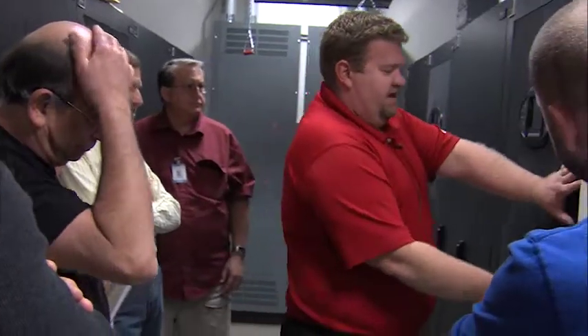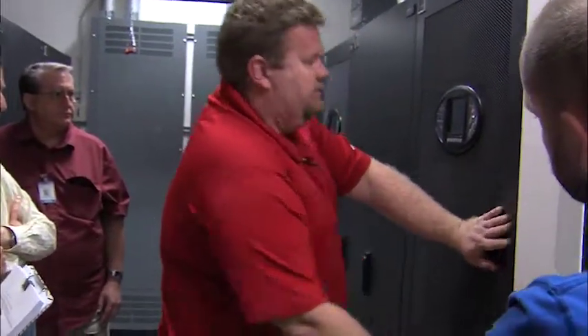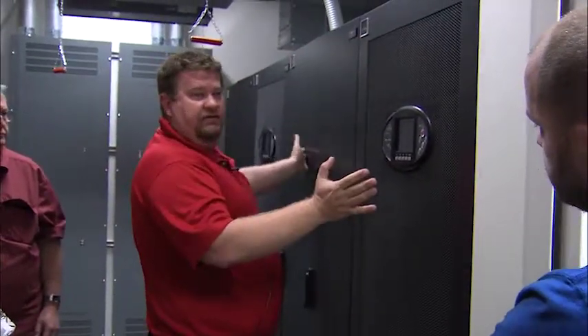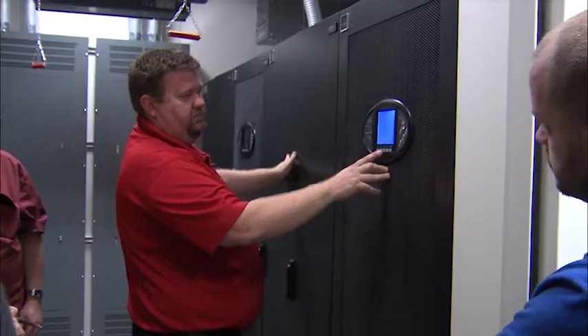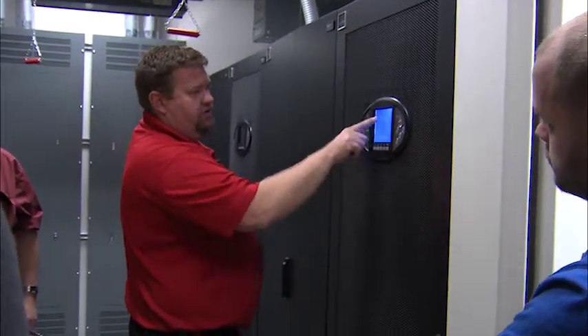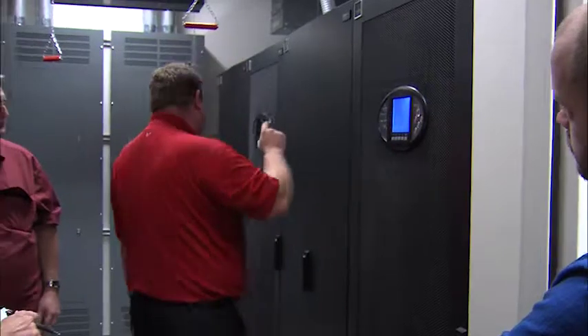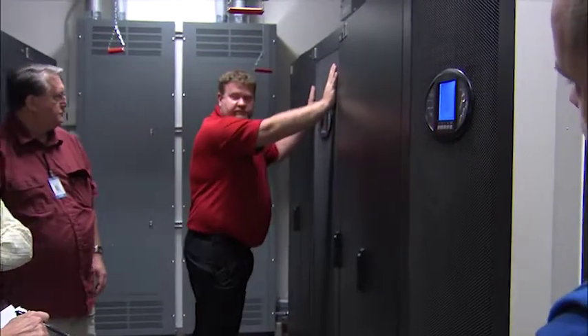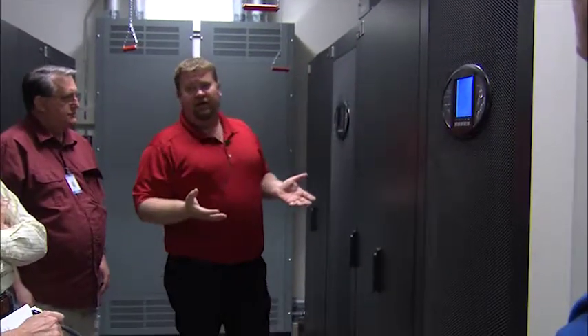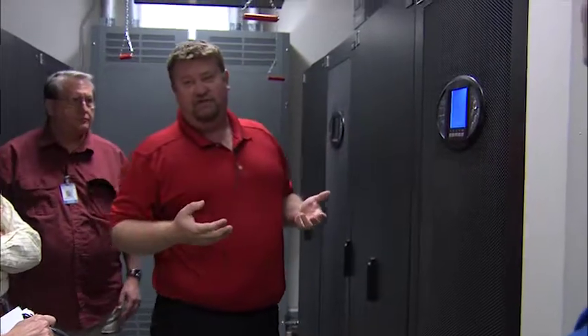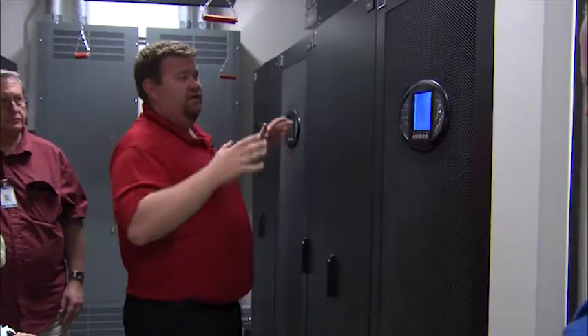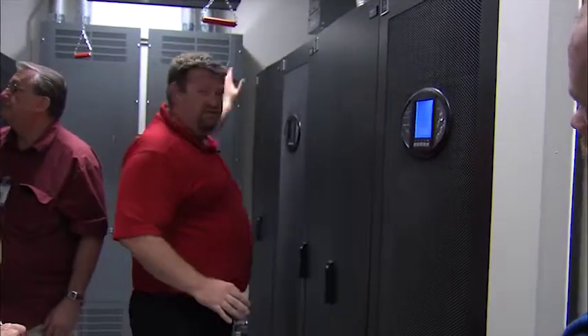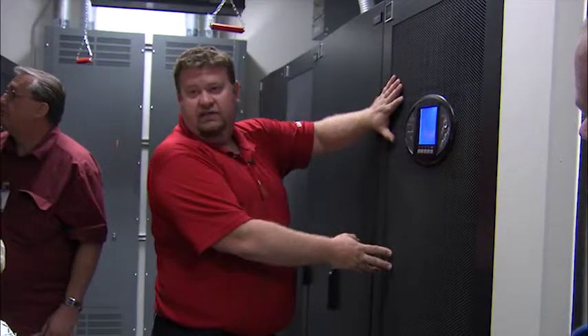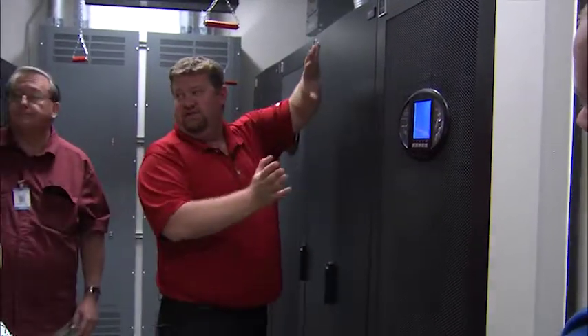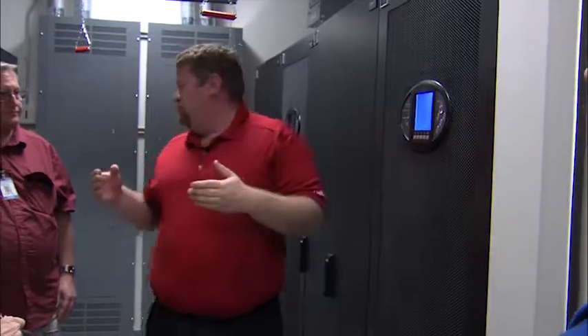So again, just to recap, this is System A, Unit 1, Unit 2, acting as parallel, what we call parallel redundant. So right now, they're sharing the load. If one system was to fail, this system would then take the whole load. And that's just on the A side. And maybe you can, I just don't recall.